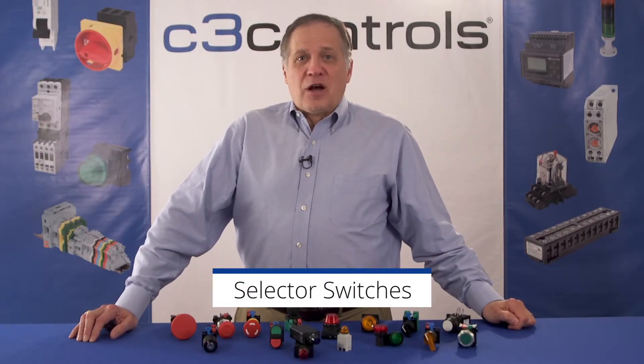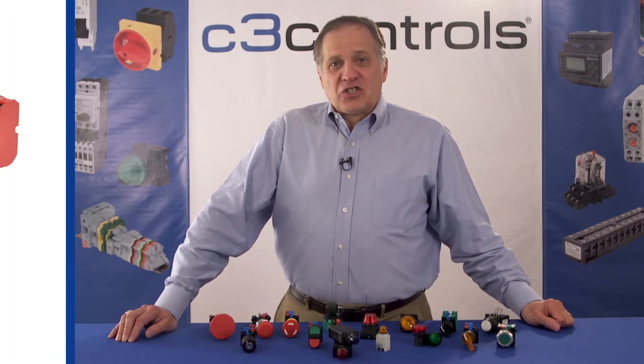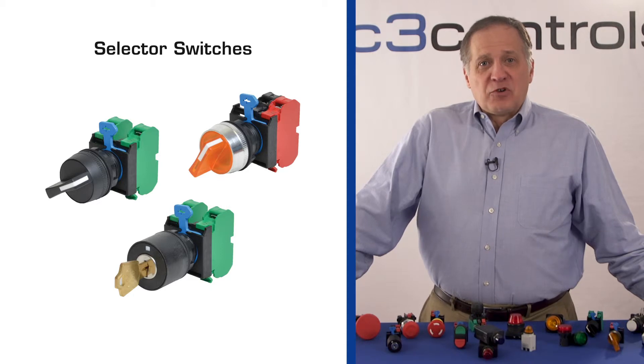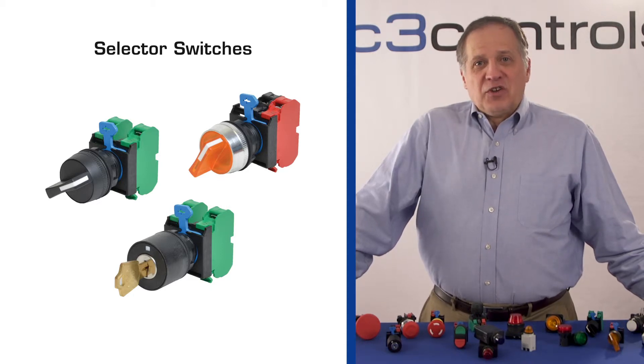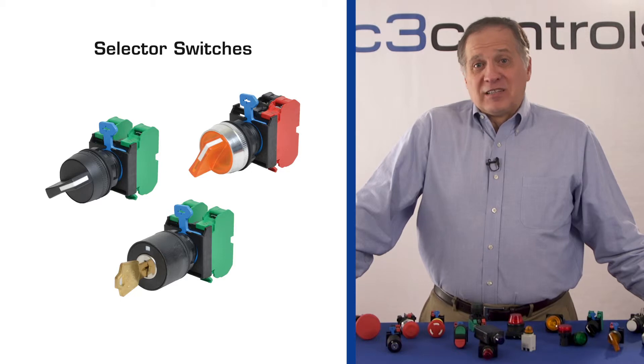Selector switches are rotary devices used to close or open contacts manually. Typically available in designs such as spring return, maintained, or key operated types, selector switches differ from push buttons only in their operation. Selector switches feature levers or knobs that are rotated to open or close the contacts, whereas push buttons operate linearly and have buttons for performing the same task.